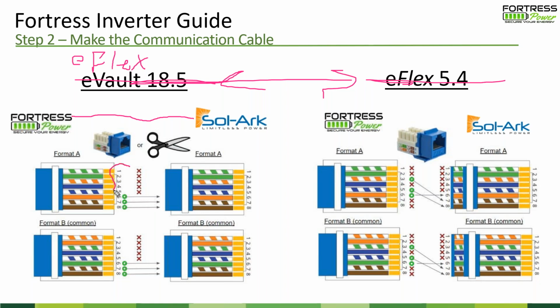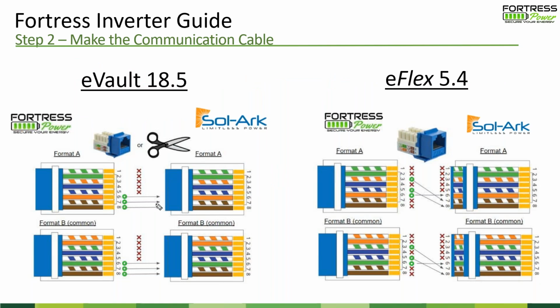On these other Ethernet pins, we use other kinds of communication that, if they were to land on the communication port for the Sol-Ark, would be garbled. The Sol-Ark inverter wouldn't know how to interpret that data, resulting in a communication error. So the simple solution is to cut into the cable and snip out wires 1 through 5, only keeping wires 6, 7, and 8.